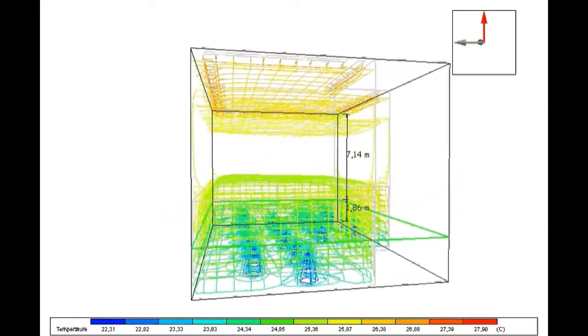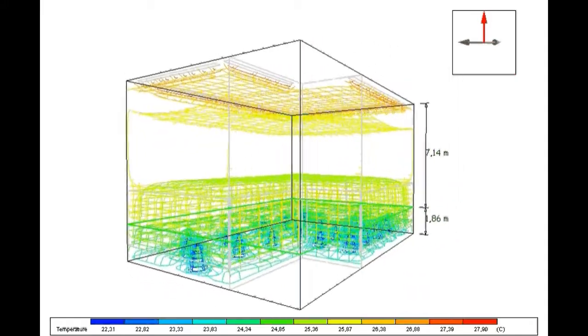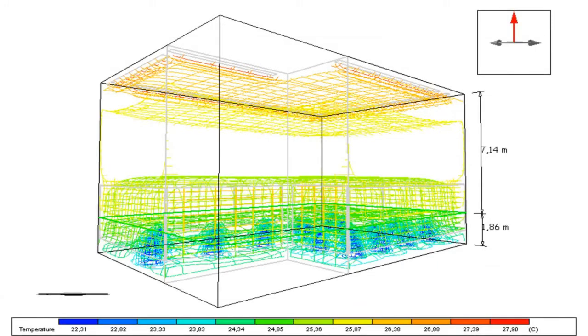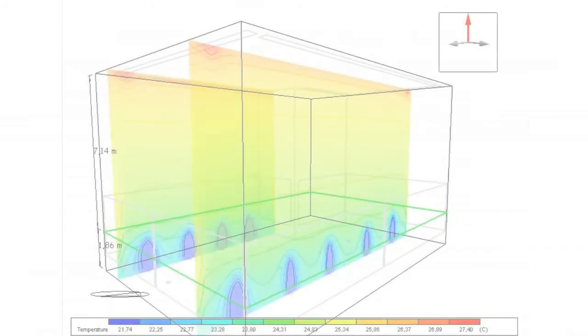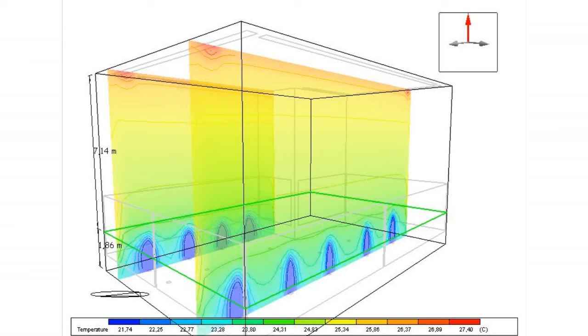A significant increase in total airflow of 180 liters per second was necessary to meet the required conditions, to ensure the right comfort conditions in the occupied zone. The most important advantage is that we don't have to cool the unoccupied zone above 1.85 meters or 6 feet. So this volume is used to collect the warmer air and all the pollutants arisen from the occupied zone, and directly extracted through the air return diffusers.